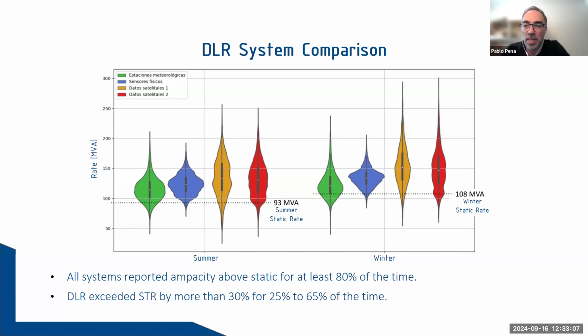Additionally, dynamic line rating exceeded the static thermal rating by more than 30% for 20% to 60% of the time, depending on the system you select. But okay, these results are statistical. What's happening in real time? How do the systems compare when faced with actual dynamic conditions?